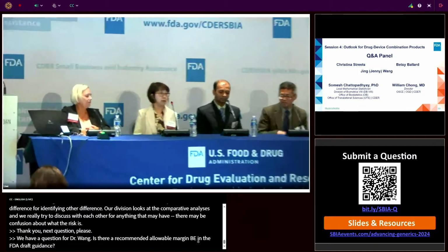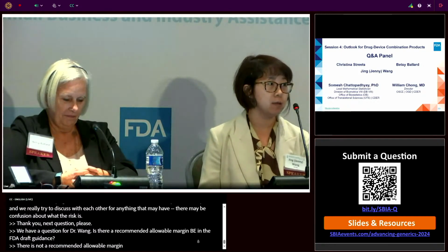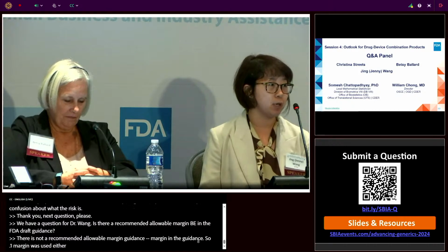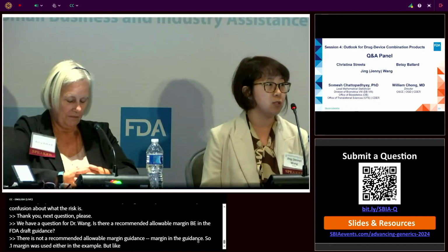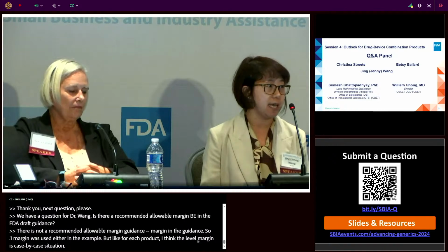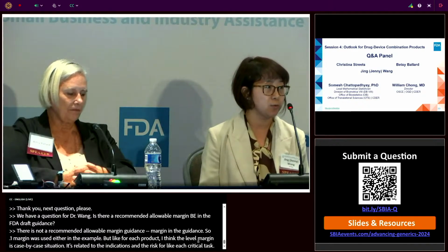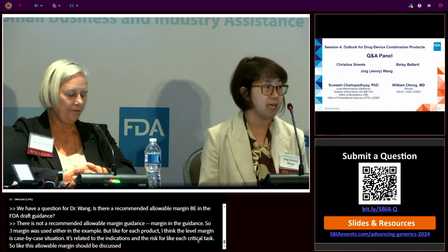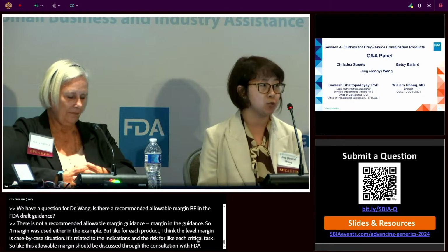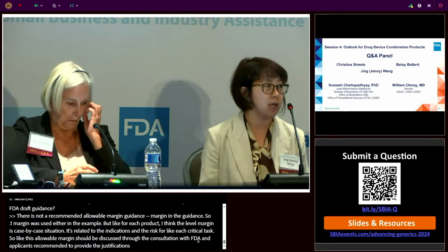There is not a recommended allowable margin in the guidance. The 0.1 allowable margin was used in the example, but for each product, I think the allowable margin is a case-by-case situation. It's related to the indications and the risk for each critical task. So this allowable margin should be discussed through consultation with FDA, and the applicants are recommended to provide the justifications and the evidence for their proposed allowable margin.